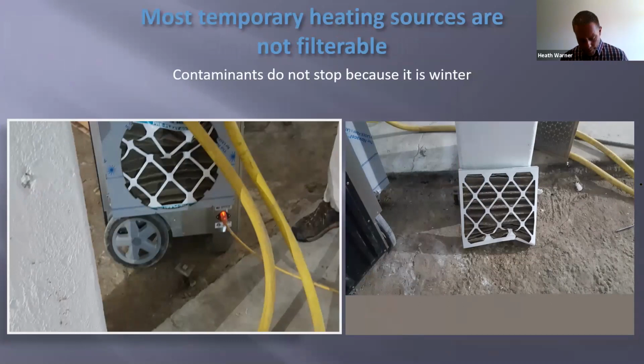Even temporary heating. Most temporary fuel heat sources, where we talk those direct flames or indirect flames, you can't run a filter on them. There is one heating source on the market that you actually can run MERV filtration. But just because it's winter doesn't mean job sites are gonna stop producing contaminants. This filter is so clogged up that it's literally crushed itself in. What was amazing was that this unit continued to function with not being able to breathe at all. Most of the time that'll burn out. But the same thing goes for if you're using your permanent system during the winter. If you're not keeping those filters clean, you're not gonna have a functioning unit. Eventually you're gonna cause all kinds of damage.